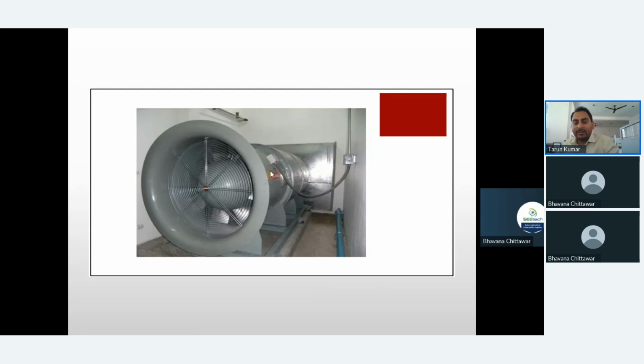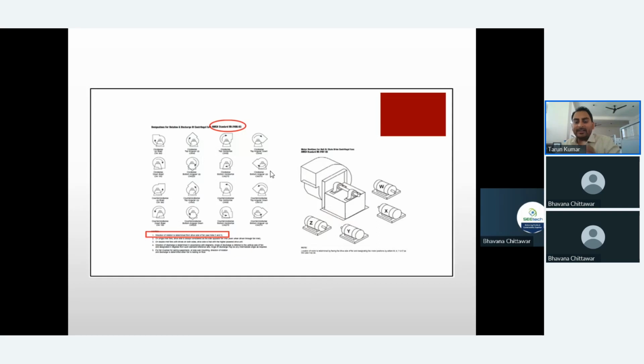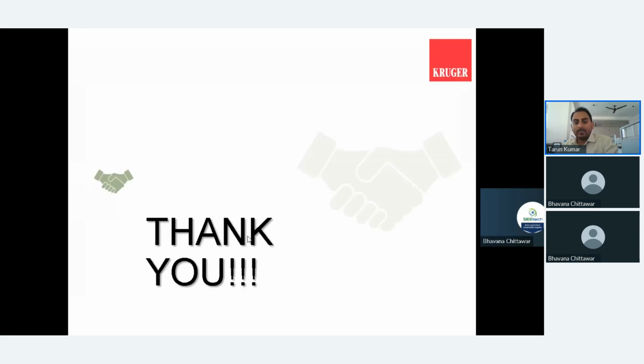At the same time, when we go for an axial fan, we should go with an arrangement where your duct is always straight. And here are the orientation details, which are available with Kruger and almost all the manufacturers. So try to take the right orientation for your fan to get the maximum efficiency from it. That's all from my side on system effect. Thank you so much. If there are any further queries on system effect, we can answer them.